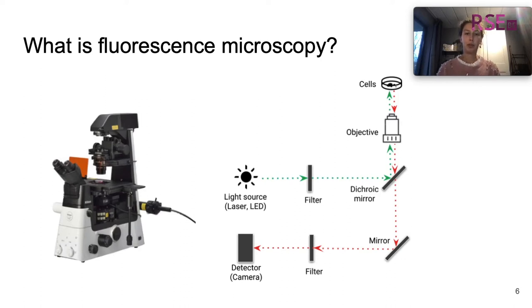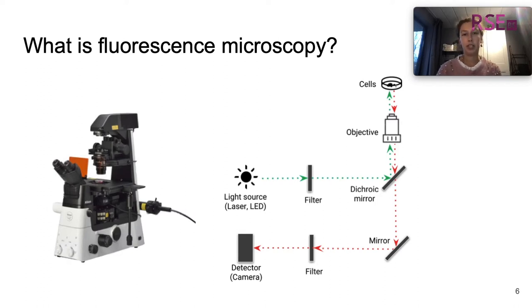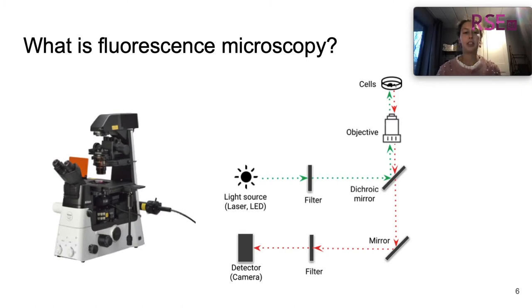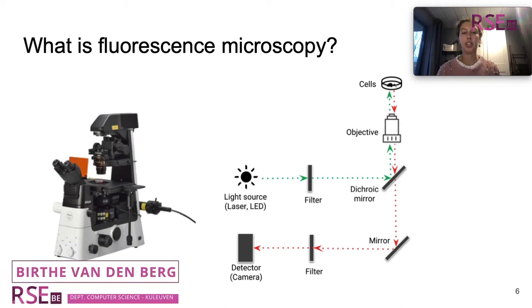We reflect on a dichroic mirror and pass through the objectives going to the cells. If these cells are fluorescently labeled, they will absorb the light that they are exposed to and emit a different color of fluorescent light. This fluorescent light will pass through the objectives and through the mirrors, through another filter to the detector, which is usually a camera. This last filter is called the emission filter, and it should filter out all noise, environmental light, or excitation light in order to only detect the fluorescent light at the camera.